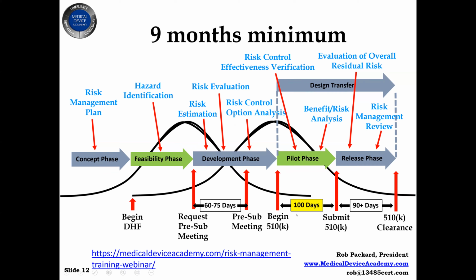It only takes us a week or less, but because it takes 100 days for you to do the testing during this verification and validation stage, and we're typically putting together the 510K in parallel with the testing during that 12-week process. So this is 12 weeks, and this is probably more like 16 weeks. So you've got a 3-month period here and probably a 4-month period here.